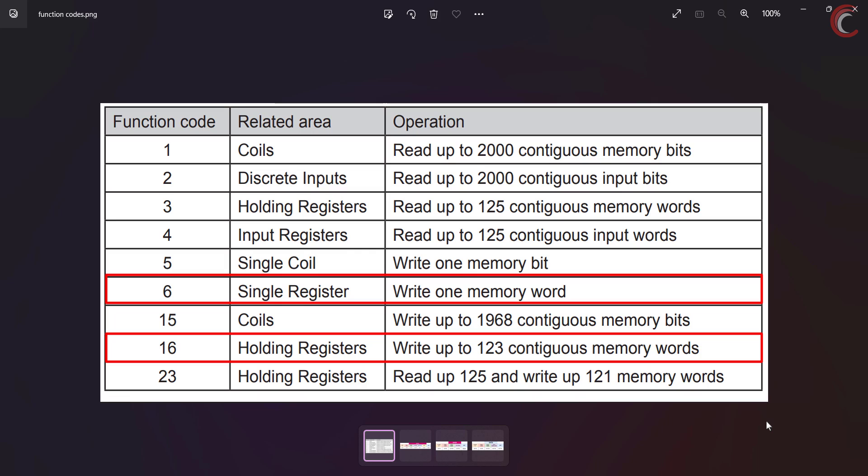The function code 6 is to write a single register, where the master can write only one memory word, that is 16 bits. The function code 16 is to write multiple registers, but the master can request a maximum of 123 registers.